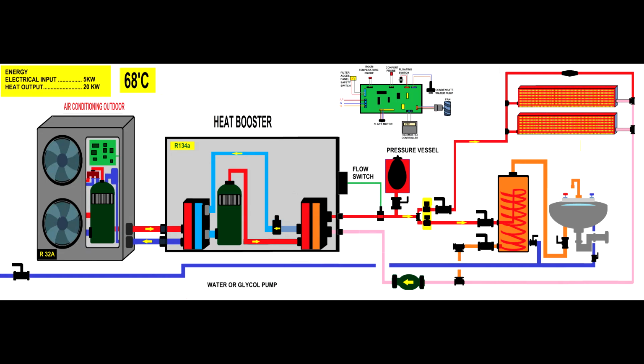But that wasn't enough, and I was thinking about a cascade system. So this time I'm using two types of refrigerants. The outdoor unit needs a refrigerant which runs on a high pressure. So that will be an R32 refrigerant. That refrigerant R32 is cooled by the refrigerant R134a, which is inside the home. That's a heat booster. Why did I do this? Well, I think 47 degrees Celsius wasn't enough. And with this heat booster, I managed to bring the temperature up to 68.